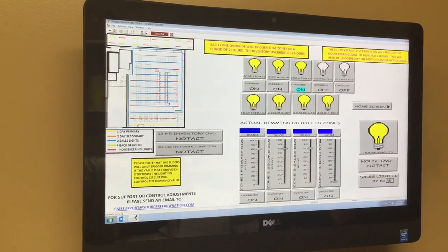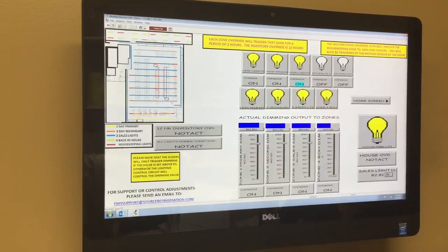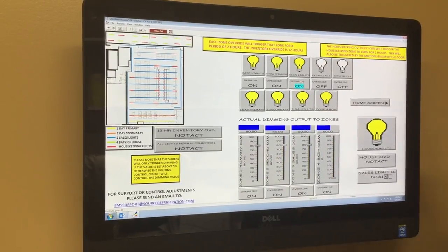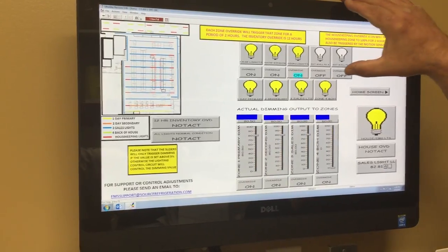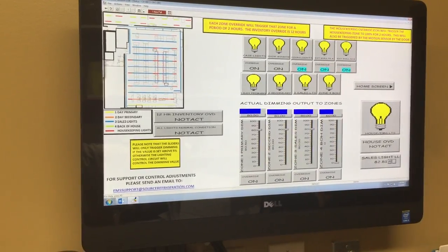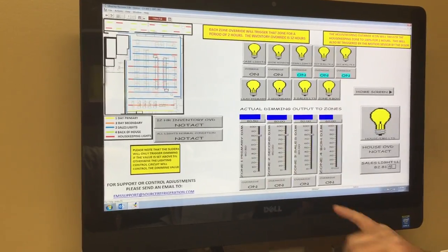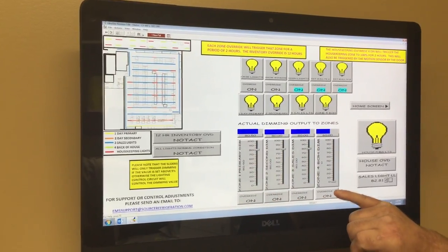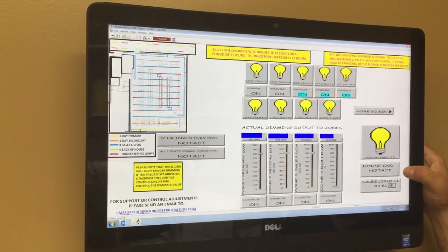Lighting controls allow us to dim, control the lights in the store, override the lights if we wanted. Exterior wall pack A and B, as an example, on the back loading dock. I can push those buttons and it will give us a 2-hour override to allow the lights to operate. Same as on the sales floor lights here or back of house lights. This is called a housekeeping override.